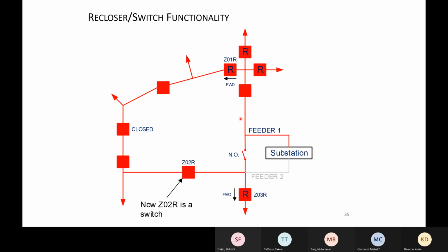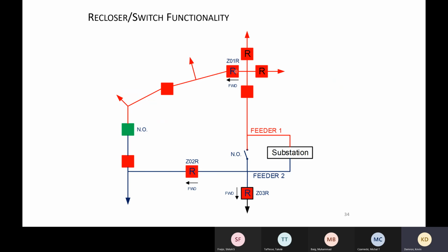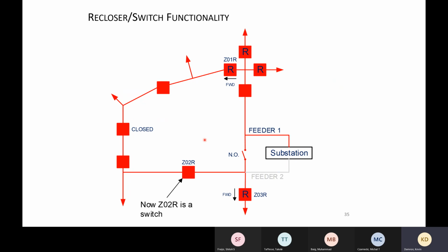So what we can do is close this normally open tie, because, say I'm working on my substation feeder breaker, I can't coordinate a lot of different devices. If we look, here I've got a forward device, and here's already a forward device. When I close that switch, now I've got a forward device, then this would be a reverse device, and then a forward device.